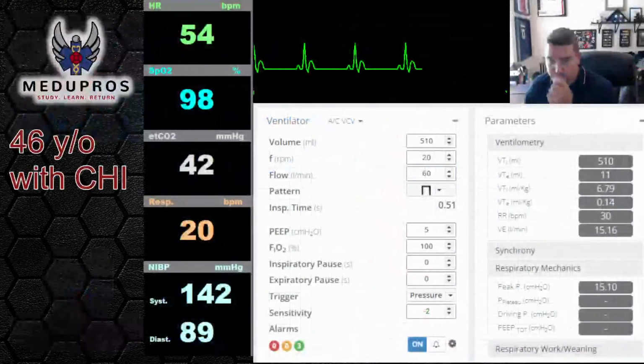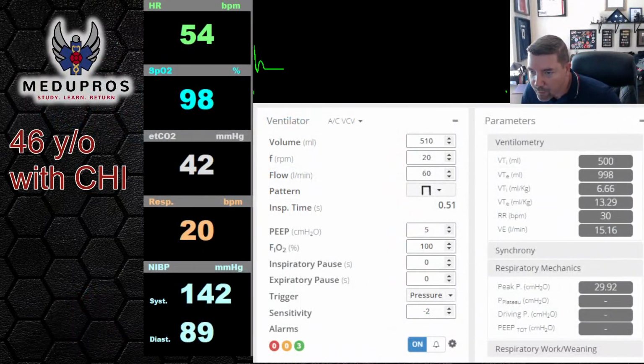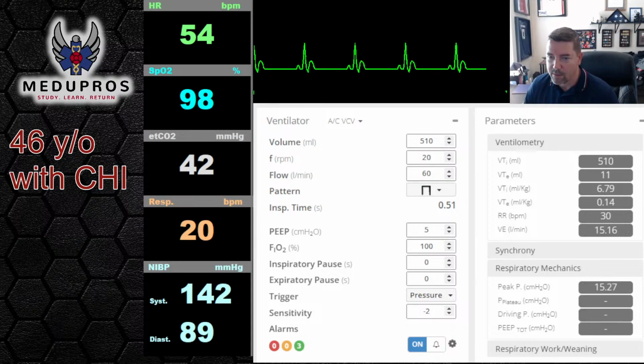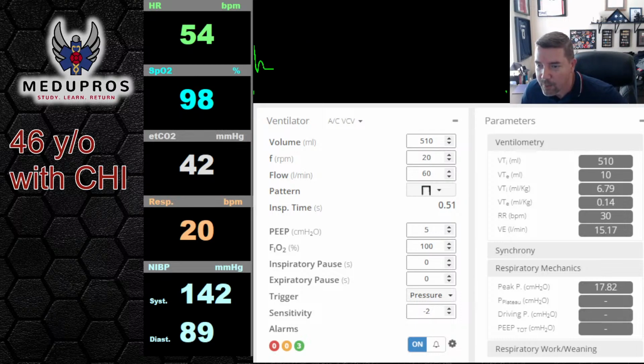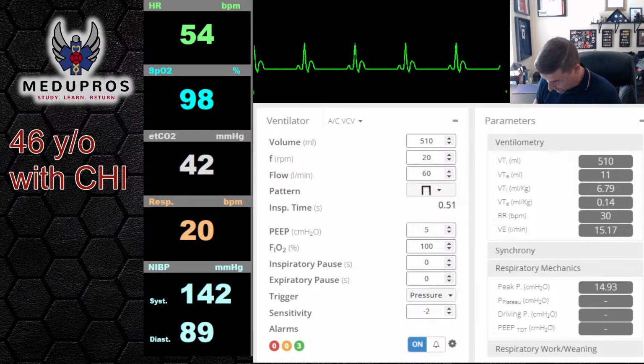All right, and then we look at frequency, respiratory rate. Good gosh. Okay, so 30 is what. They're supposed to be set at 20 here, right? But they're really breathing 30. So what I need to go do, just as a point of order, is make sure that this reads 30, just like this reads. So my bad. We're working on this, Jacob. We're getting better, buddy. Okay. So here we're actually breathing 30, even though we've set 20, right? We've set 20.